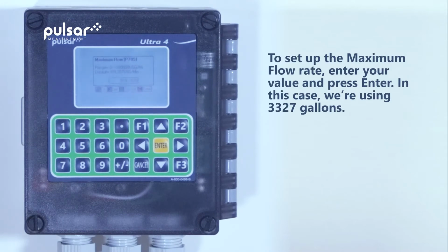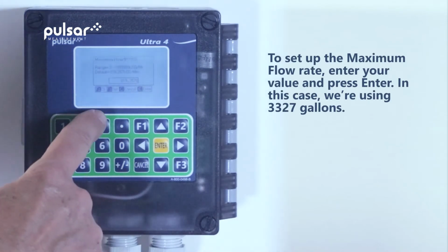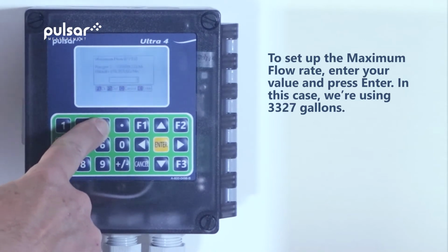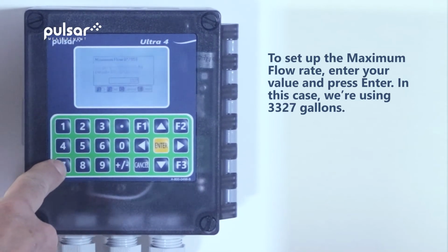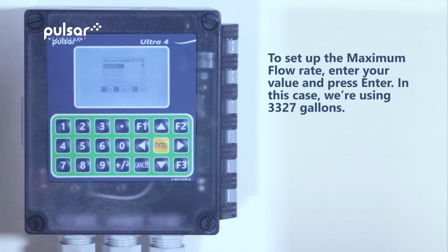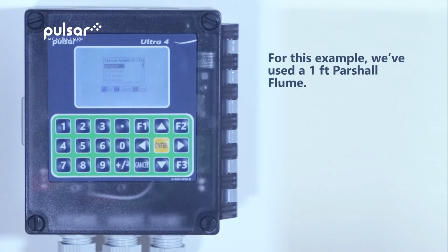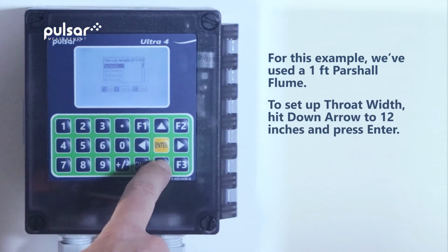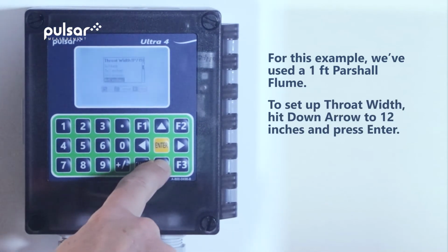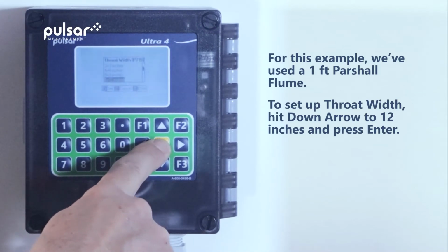Now it's time to set up the maximum flow rate for the parameters that we previously set. In this example, we'll set a maximum flow rate of 3,327 gallons and then hit enter. For this example, we've used a 1-foot Parshall flume. Now it's time to set up the throat width of the Parshall flume. In this case, it's 1 foot or 12 inches. We'll hit the down arrow button to 12 inches and then hit enter.